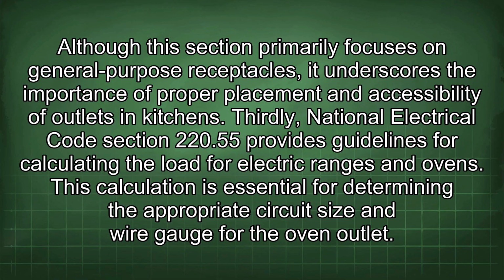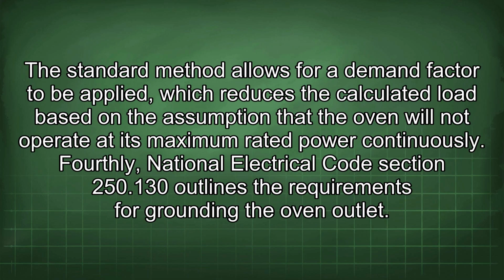This calculation is essential for determining the appropriate circuit size and wire gauge for the oven outlet. The standard method allows for a demand factor to be applied, which reduces the calculated load based on the assumption that the oven will not operate at its maximum rated power continuously.